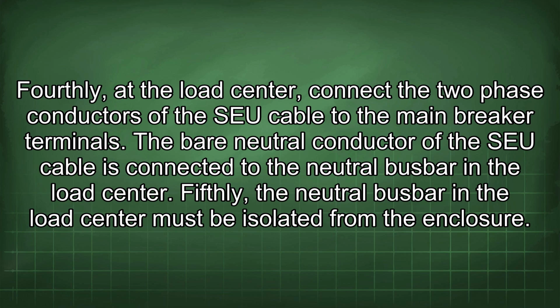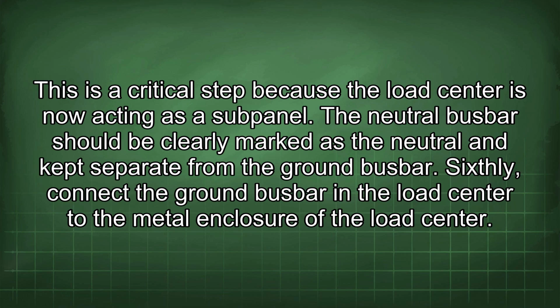Fourthly, at the load center, connect the two phase conductors of the SEU cable to the main breaker terminals. The bare neutral conductor of the SEU cable is connected to the neutral busbar in the load center. Fifthly, the neutral busbar in the load center must be isolated from the enclosure. This is a critical step because the load center is now acting as a subpanel. The neutral busbar should be clearly marked as the neutral and kept separate from the ground busbar.